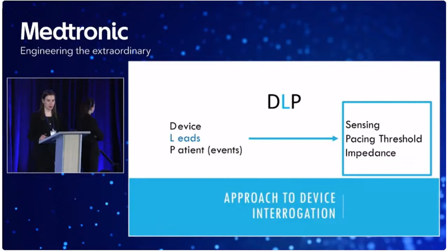So in terms of some background, sensing is the ability of the pacemaker to see when intrinsic depolarization is occurring. So the electrode senses the intrinsic electrogram, and if it senses it, it can inhibit pacing. Pacemakers sense depolarization by measuring changes in the electrical potential of myocardial cells between the anode and the cathode. So in an atrium, if we're looking for an acceptable P wave, we're typically looking for it to be big, but above 1 millivolt would be acceptable.